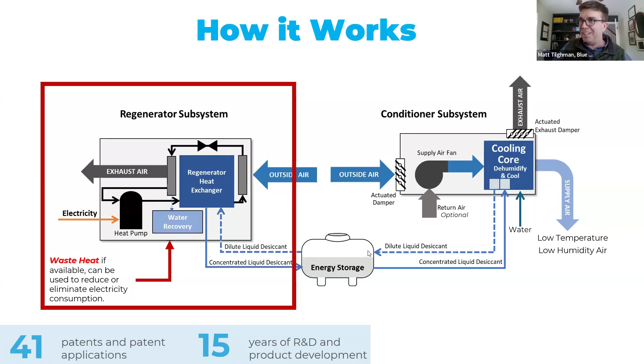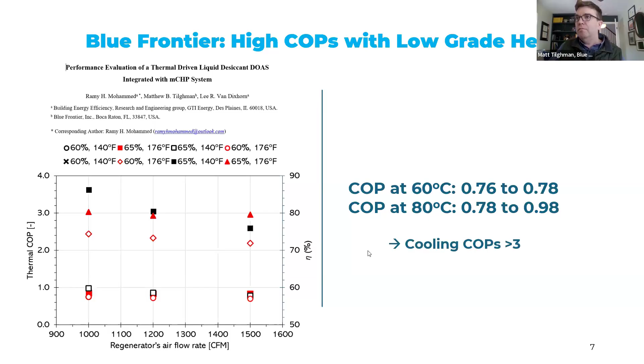So this is low-grade waste heat of the type that NVIDIA is saying can come out of their chips, getting you meaningful COPs. And these are thermal COPs, meaning the amount of moisture removed from the desiccant. When you map that on to the actual air conditioning, because the drying of the air enables follow-on indirect evaporative cooling, it's COPs of about 3 and greater, based on the waste heat. So why is that meaningful for a data center?